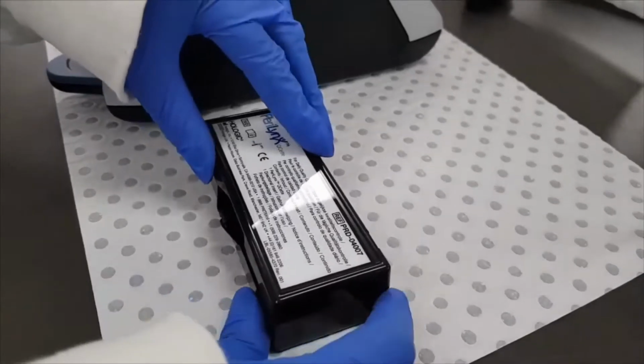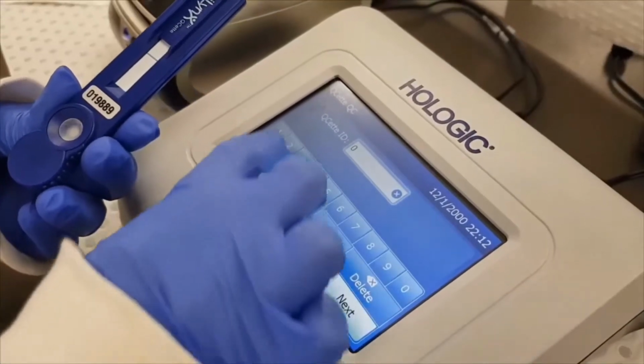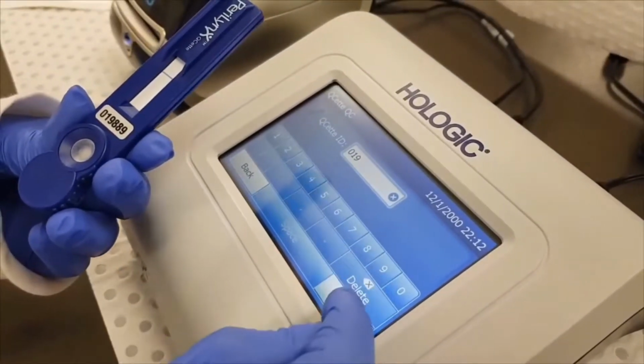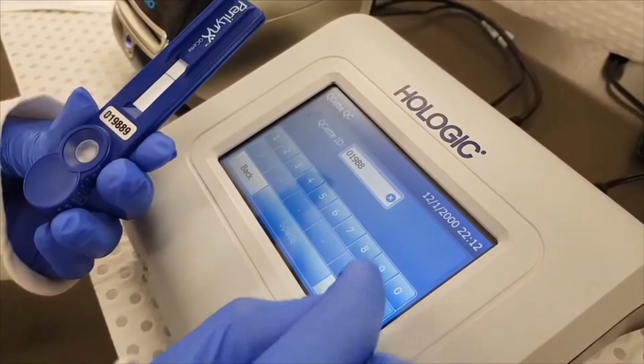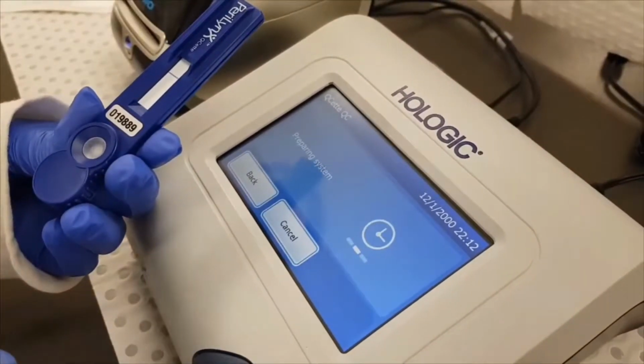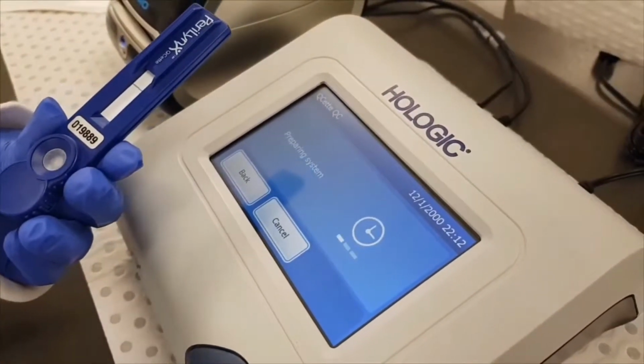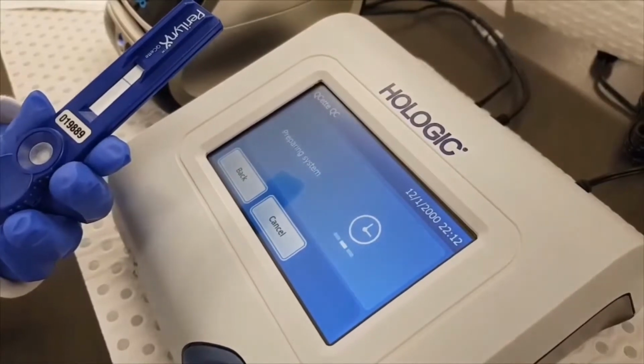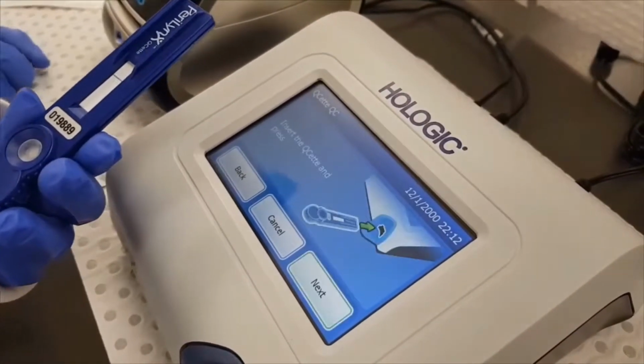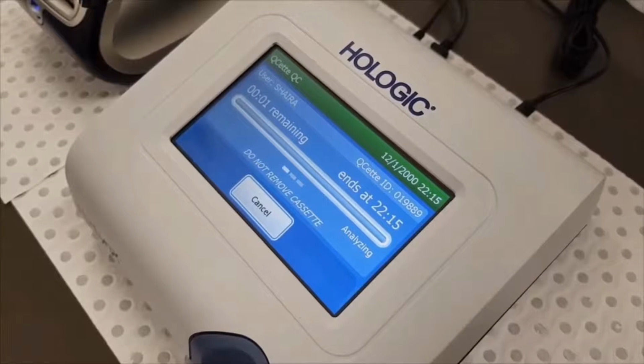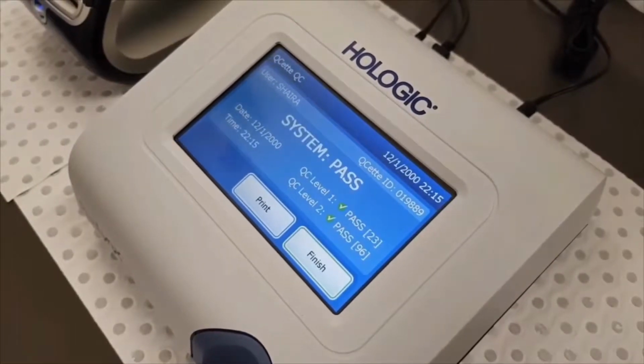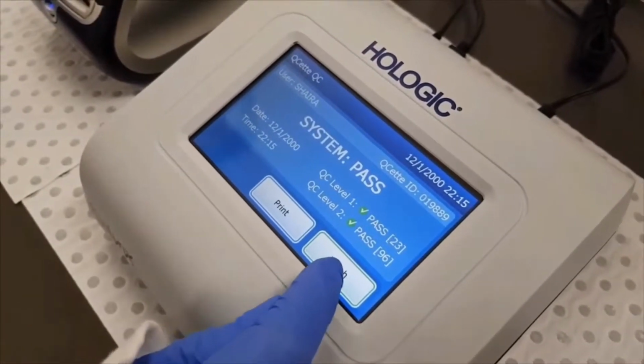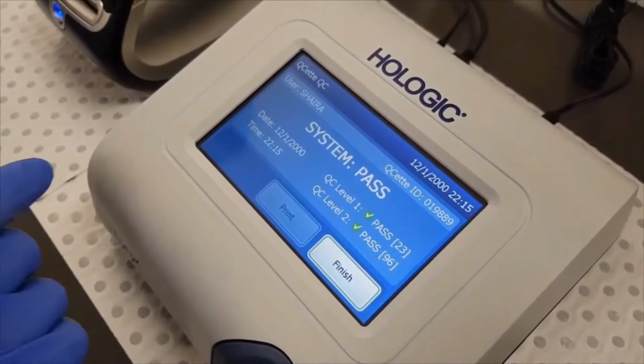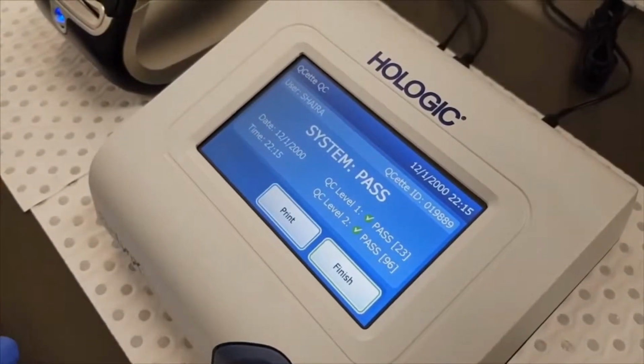Take the QCette and select Run QCette QC from the main menu and enter the 6-digit ID as labelled on the device. This is the start of the quality control, which is completed once a day before patient testing. Press Next and insert the QCette for analysis. Once passed for level 1 and 2, select Print to keep for your own records and press Finish.